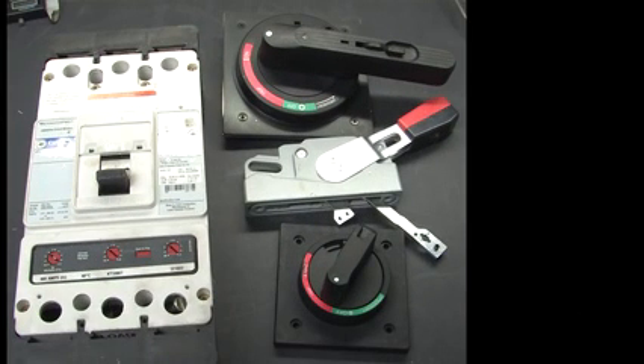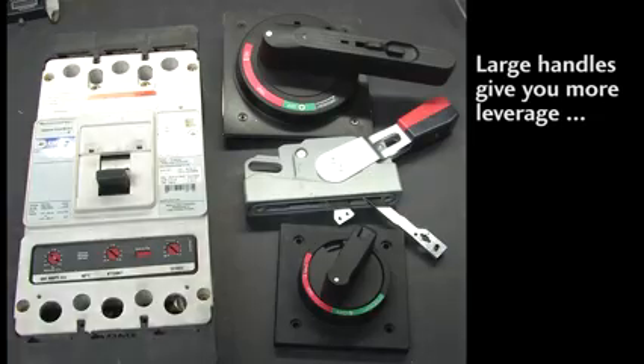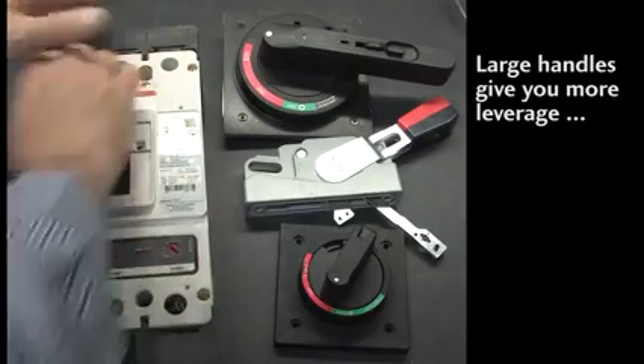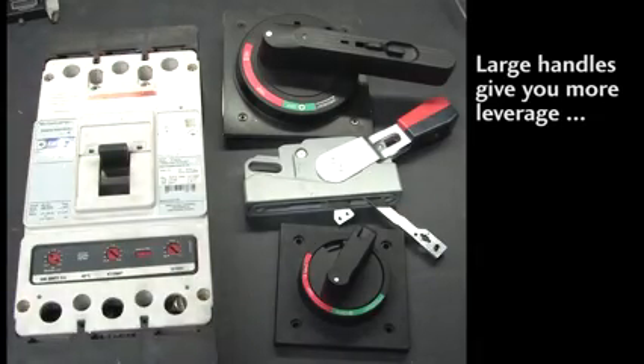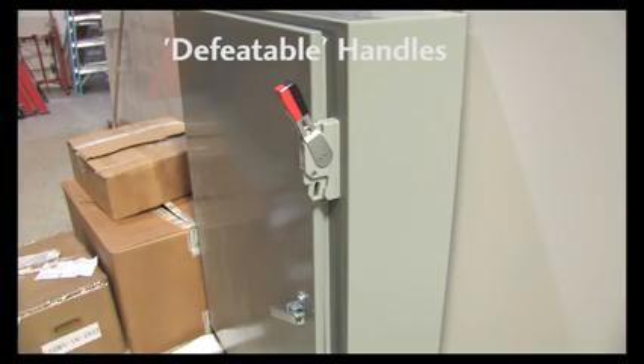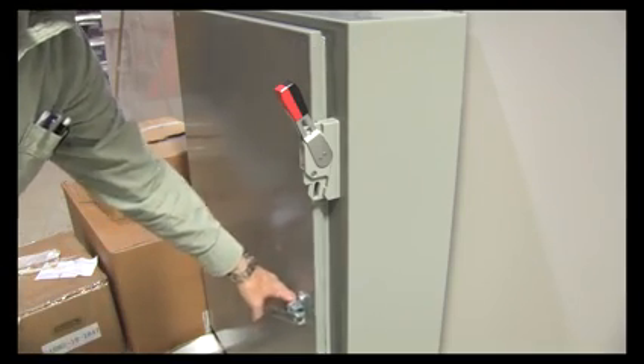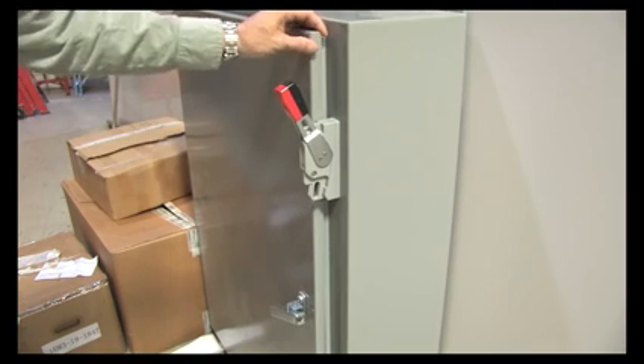Both of these remote handles give you one other advantage. They make it easier to flip the breaker switch, so you don't have to go get a pair of vice grip pliers just to reset the breaker, especially on those large breakers. Note that some of these are referred to as defeatable. Normally, the switch won't allow you to open the cabinet until the power is off.